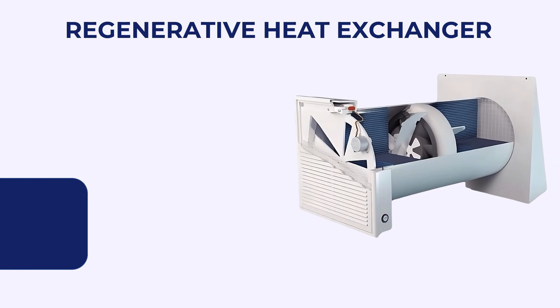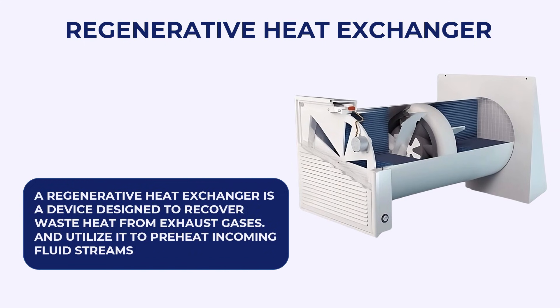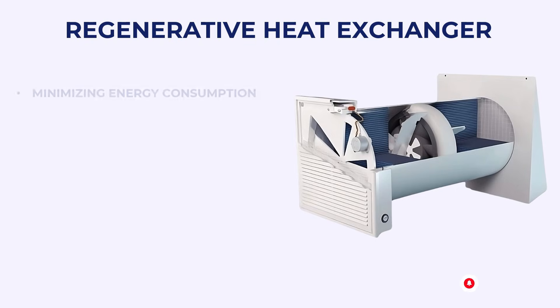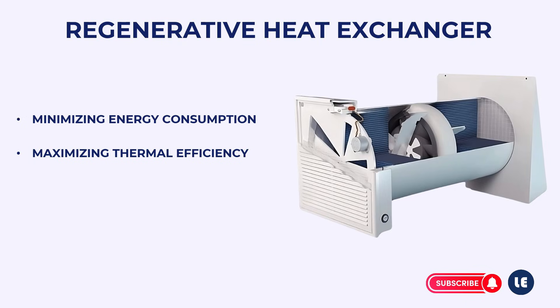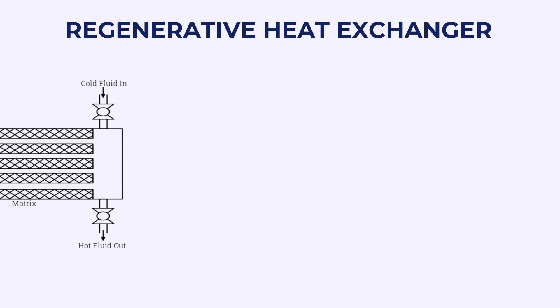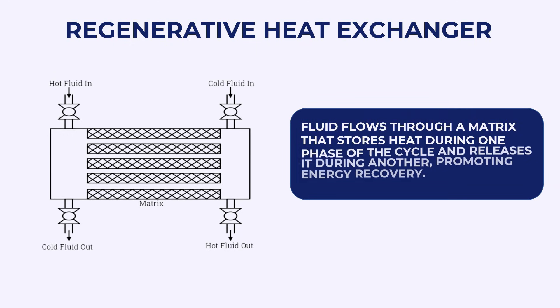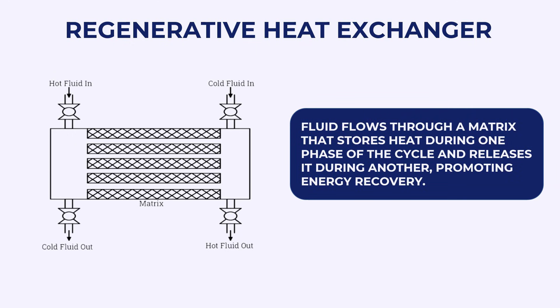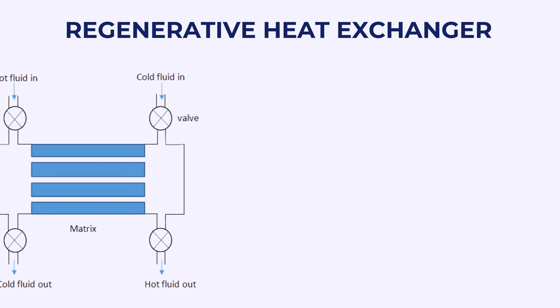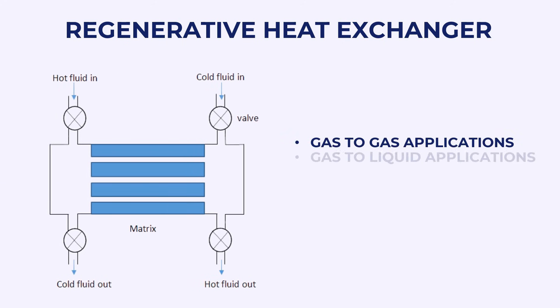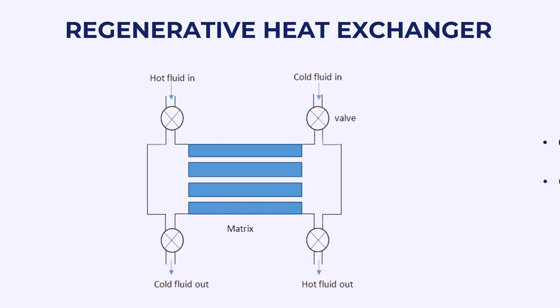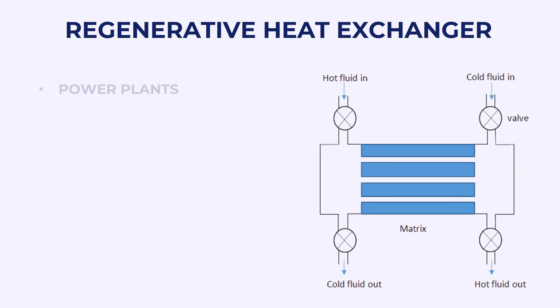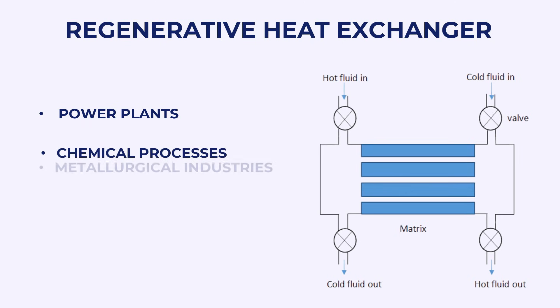Regenerative Heat Exchanger. A regenerative heat exchanger is a device designed to recover waste heat from exhaust gases or process streams and utilize it to preheat incoming fluid streams, thereby minimizing energy consumption and maximizing thermal efficiency. Fluid flows through a matrix that stores heat during one phase of the cycle and releases it during another, promoting energy recovery. Regenerative heat exchangers are commonly used for gas-to-gas and gas-to-liquid applications, and are found in power plants, chemical processes, and metallurgical industries.